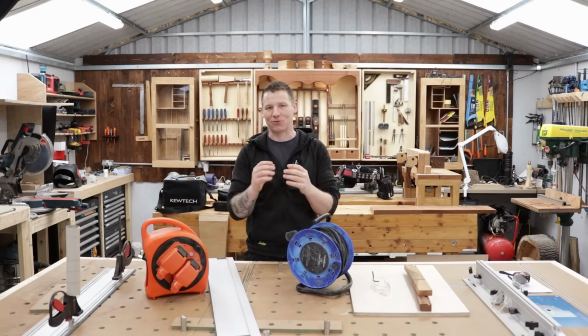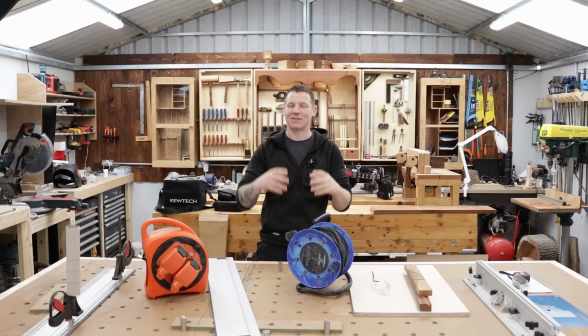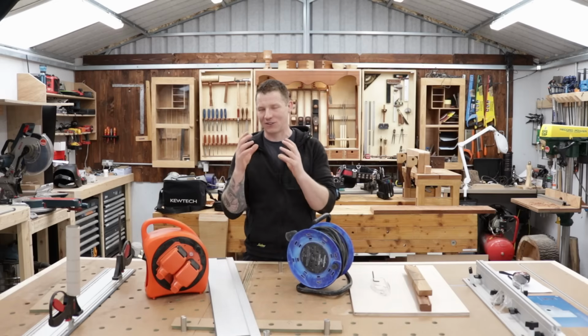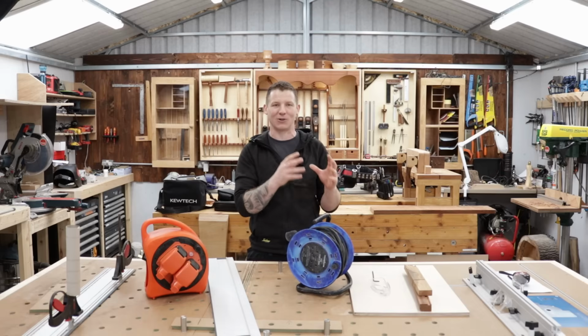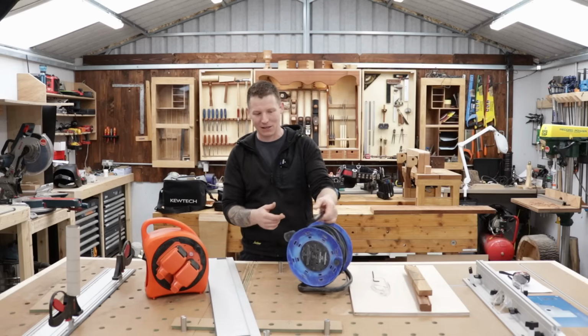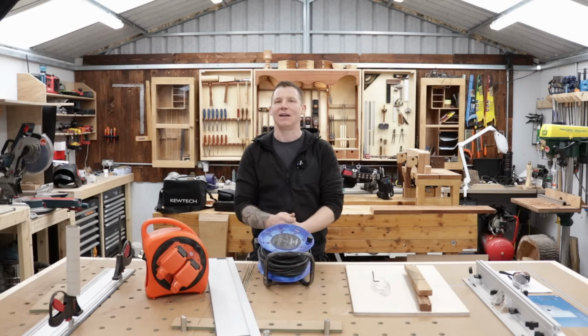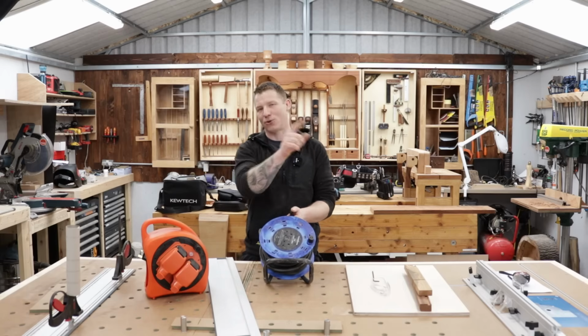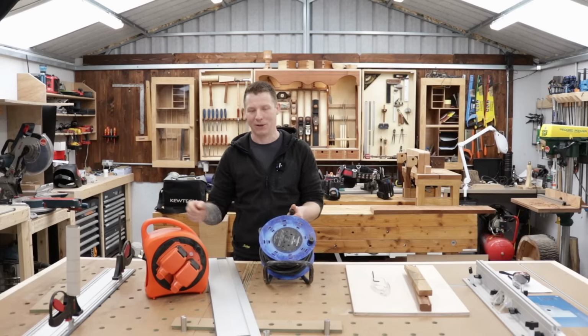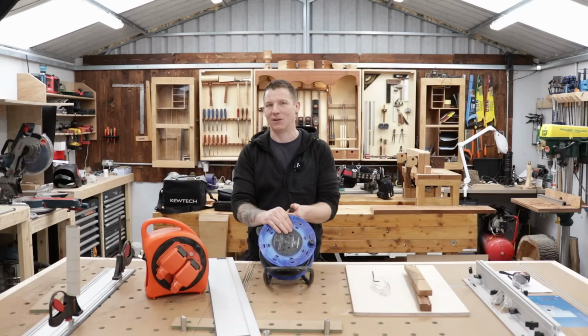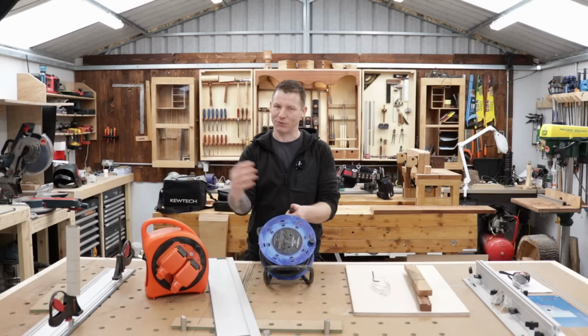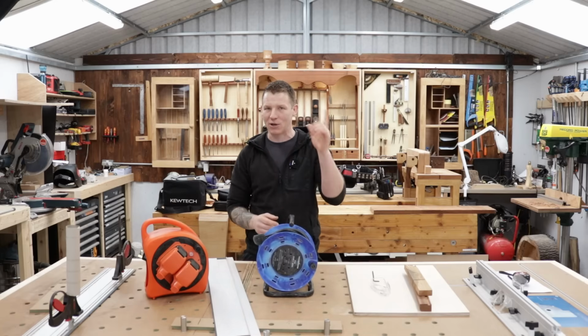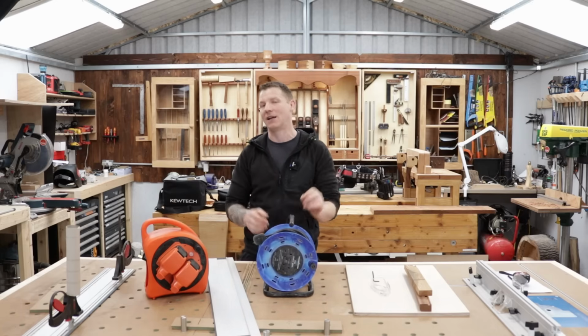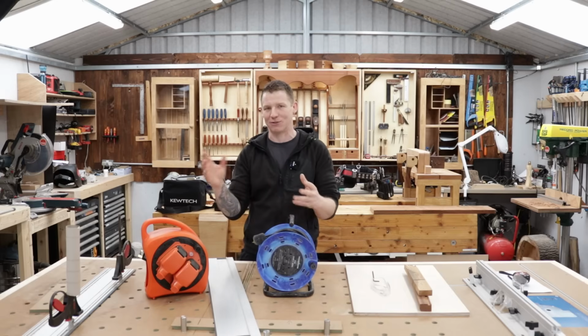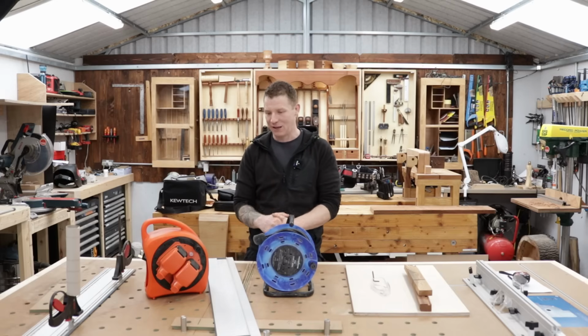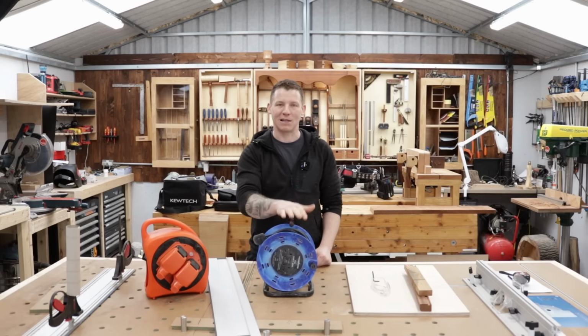So something I want to try and drum into you guys as you're watching this video, it's not just the load on the circuit, it's not just the thing that you're plugging in, it's the distance of that circuit as well, and it's fundamentally important. So you think about it, that's a 20-meter extension lead, and if I plug that into the last socket or the furthest socket from my board in my workshop, then I've just added 20 meters now to that circuit when I plug in here. Now, if the resistance of that circuit gets too high, the breaker will not trip on short circuit. And I'll demonstrate that with the meter for you in a second. I'll give you some readings and you can see just what this does. So that's one thing to think about. They should not be left permanently in place anywhere.